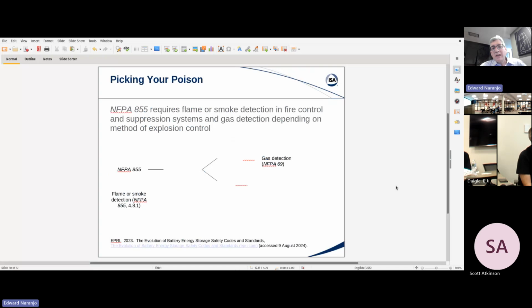NFPA 855, like other NFPA standards, are prescriptive, but to a degree. They allow for some latitude of the end users to develop the type of fire protection that they deem most appropriate. 855 simply points out that end users must equip their BESS storage system with some sort of flame or smoke detection. That's very, very important. It's only flame or smoke. So the umbrella standard just speaks to those detection technologies. However, there is a standard called NFPA 69 that does require gas detection.